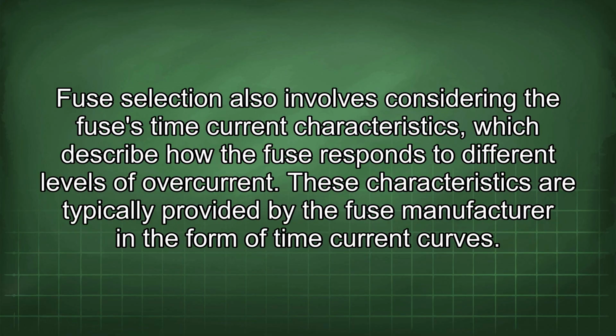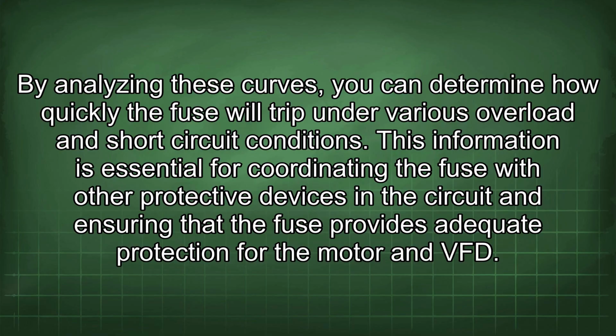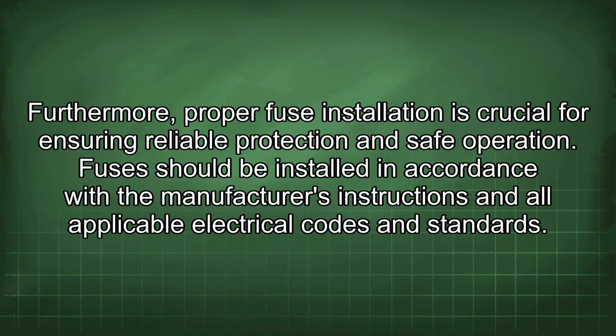Fuse selection also involves considering the fuse's time current characteristics, which describe how the fuse responds to different levels of overcurrent. These characteristics are typically provided by the fuse manufacturer in the form of time current curves. By analyzing these curves, you can determine how quickly the fuse will trip under various overload and short circuit conditions. This information is essential for coordinating the fuse with other protective devices in the circuit and ensuring that the fuse provides adequate protection for the motor and VFD. Furthermore, proper fuse installation is crucial for ensuring reliable protection and safe operation.